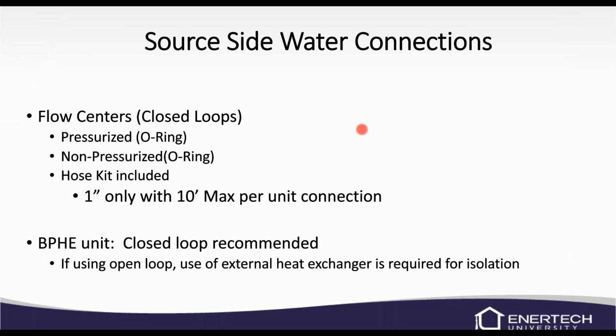Again, the source side water connections, they're all double O-ring fittings on the unit and on the flow centers. So you've got to have a double O-ring connection or connectors on it. That's going to come with the unit, so there's no reason for you to use anything else.